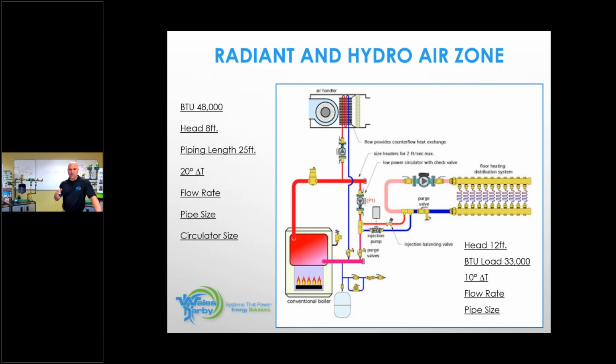So this is why we're going through these exercises, so you can apply this to the real world when you're in someone's home and they have an insufficient heat call. You can find the root cause of that insufficient heat call. One of our friends said, well, we see 3/4 PEX as the pipe size. That is true. Very true, and painful. Yeah, that's a tough fix. There's no fix.